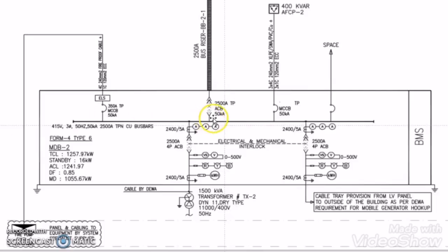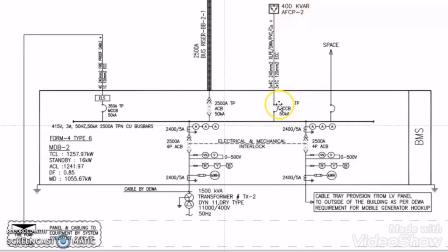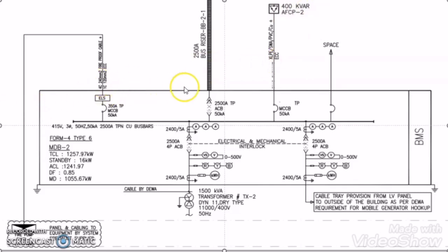For that I have taken one example. This is my LV panel and this is the capacitor bank. If you want to know how I calculated the capacitor bank size as 400 kVAR, then watch my video — the link will be in the description below. But here in this video my motive is to calculate the breaker rating and the cable size for this capacitor bank. From this SLD, the data available is that the capacitor bank size is 400 kVAR and it is a 3-phase system so the voltage is 400V.